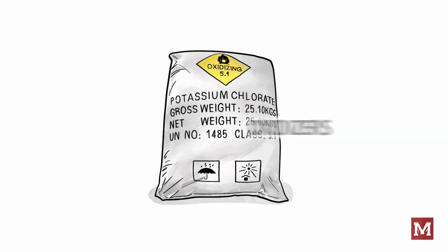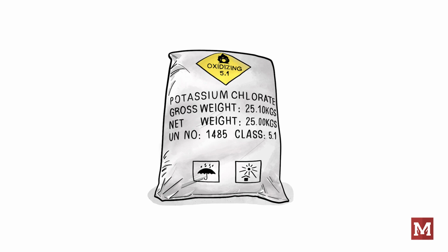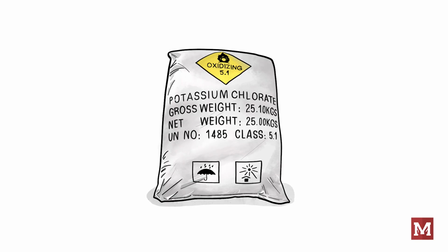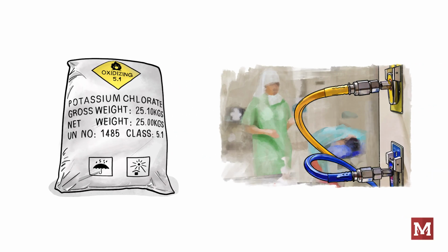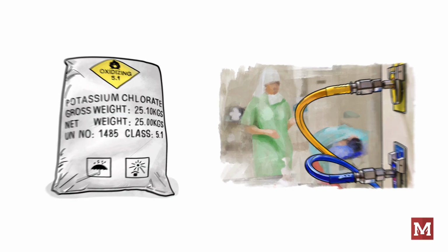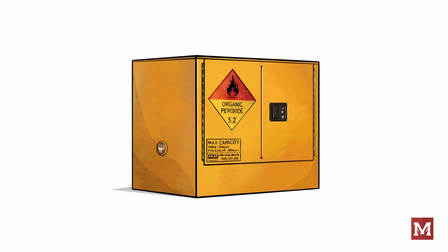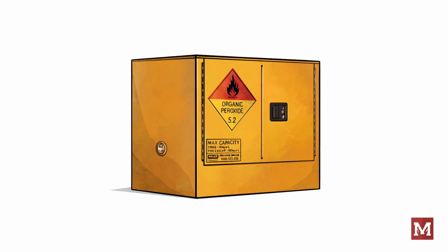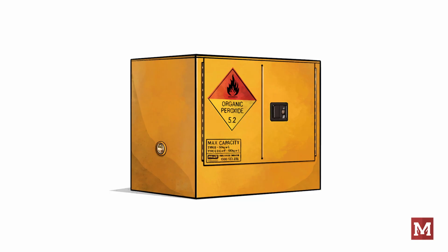Oxidizers, which include solid, liquid, and gas: these are materials that readily yield oxygen or other oxidizing substances to promote or enhance combustion of a material. They don't typically burn themselves, but they make other materials burn more intensely or require less energy to burn, creating a larger hazard. Oxygen gas is a prime example, but we also have nitrous oxide, which is common in medical and dental facilities. Organic peroxides: organic compounds containing peroxide functional groups, the O-O, which can be highly unstable and pose both fire and explosion hazards due to their combination of fuel, the organic part, and the oxidizer, the peroxide group.